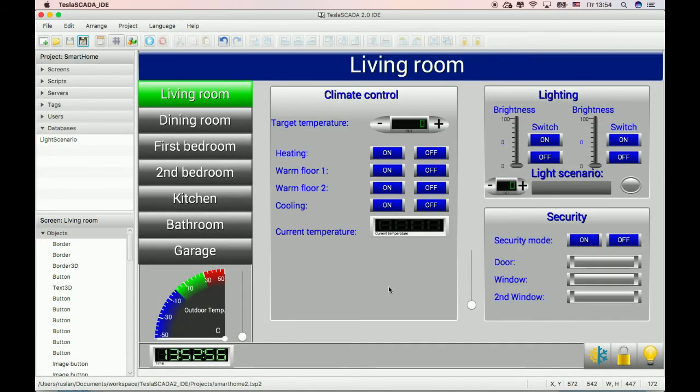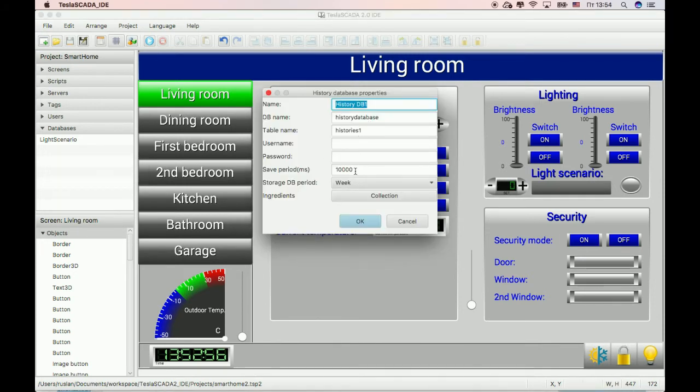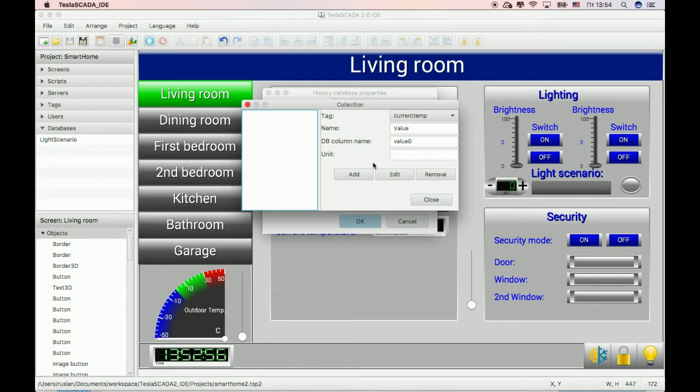Now in the new version of TeslaSCADA2, we have possibility to add history database trends. Let's create history database. Change save period to 1 second and add parameters that will save current temperature and outside temperature.